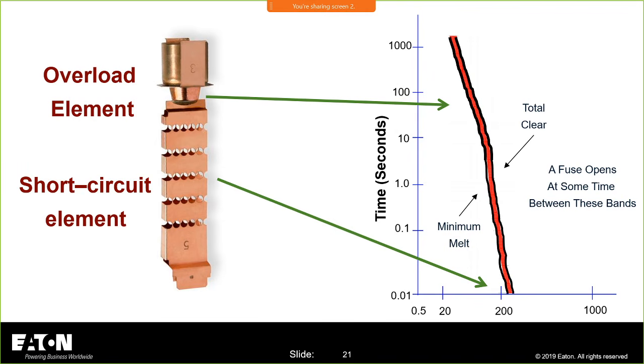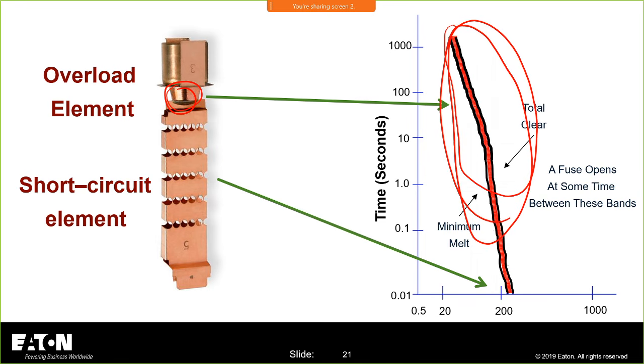Now, this is when it gets real in my ballpark, because relating that element to the trip curve of a fuse is when you really understand the benefit and the values of these things. So this overload area is all up in here, and there's a point on this curve where you start to hit these pinch points, and it's probably somewhere in this region and to the right.